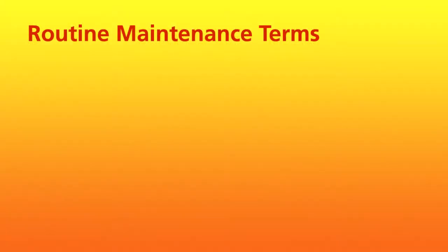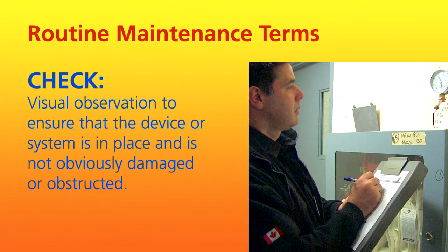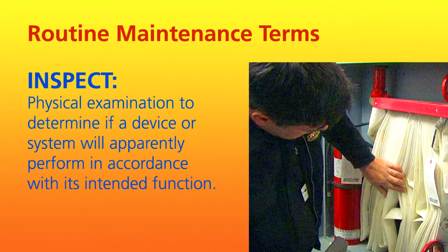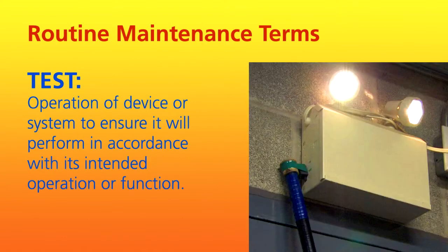In properly maintaining the fire protection and life safety elements in your building, it is important to understand the difference between three basic terms. A check is a visual observation to ensure the device or system is in place and is not obviously damaged or obstructed. To inspect is to physically examine a device or system to determine if it will apparently perform in accordance with its intended function. A test involves the actual operation of a device or system to ensure it will perform in accordance with its intended operation or function.